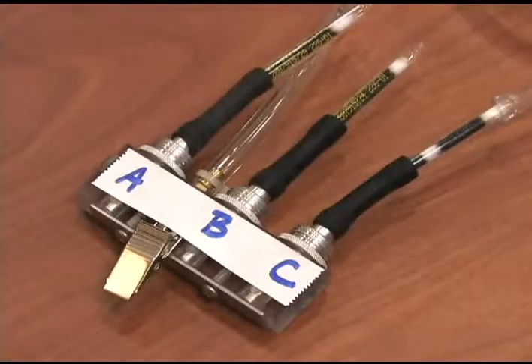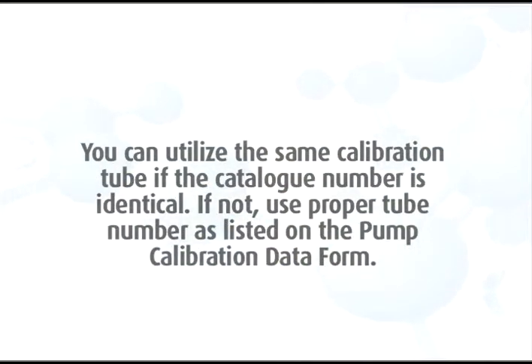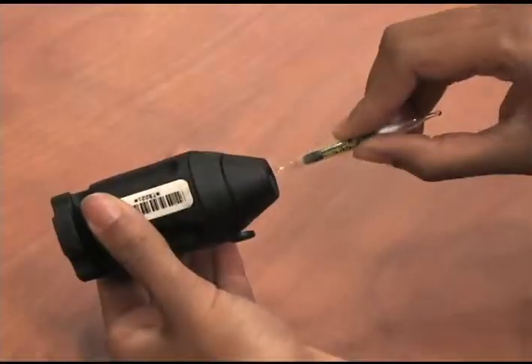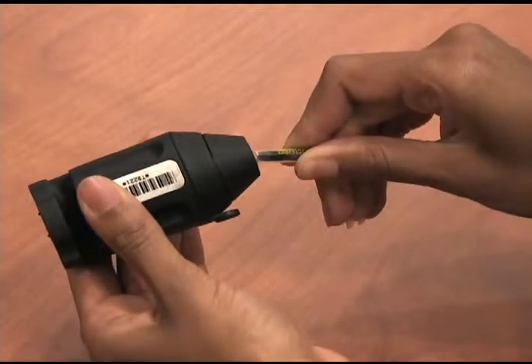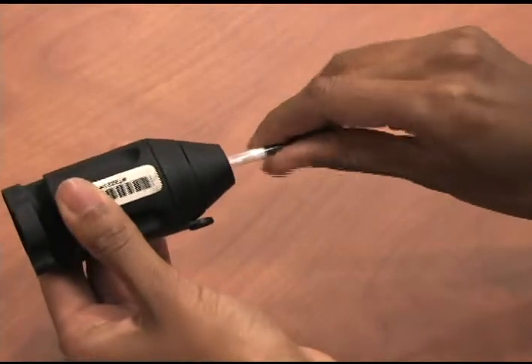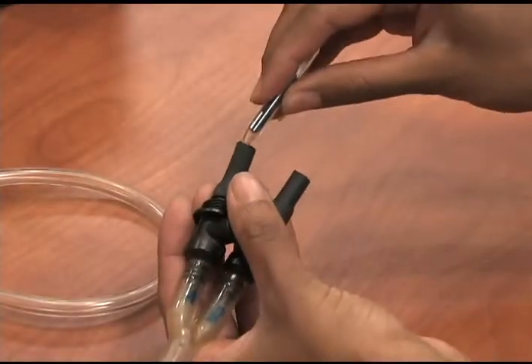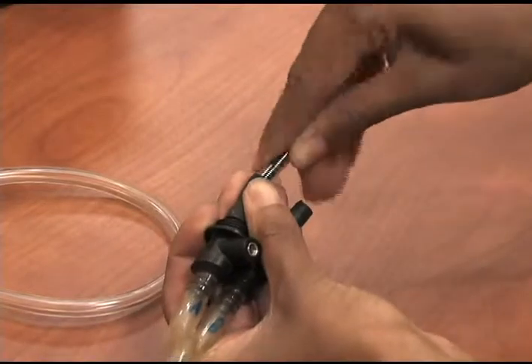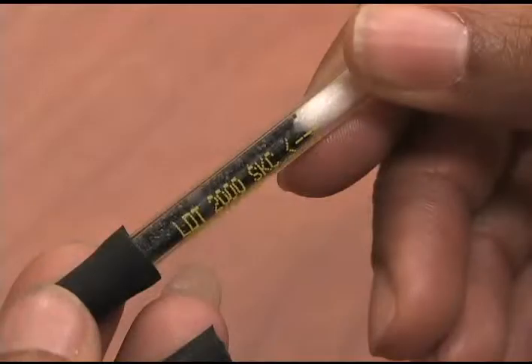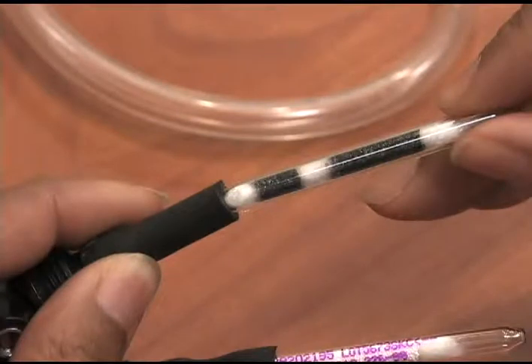The triple splitter will have 3 ports labeled A, B, and C. You can utilize the same calibration tube if the catalog number is identical. If not, use the proper tube number as listed on the pump calibration data form. Use a tube breaker to break both ends of the tube to provide an opening at least 1/2 the internal diameter. Insert the opened sorbent tube into the first holder's rubber sleeve marked A, with the arrow on the tube pointed toward the holder. If the tube does not have an arrow, then place the end of the sorbent tube with the smallest sorbent section or backup section into the tube holder toward the pump.